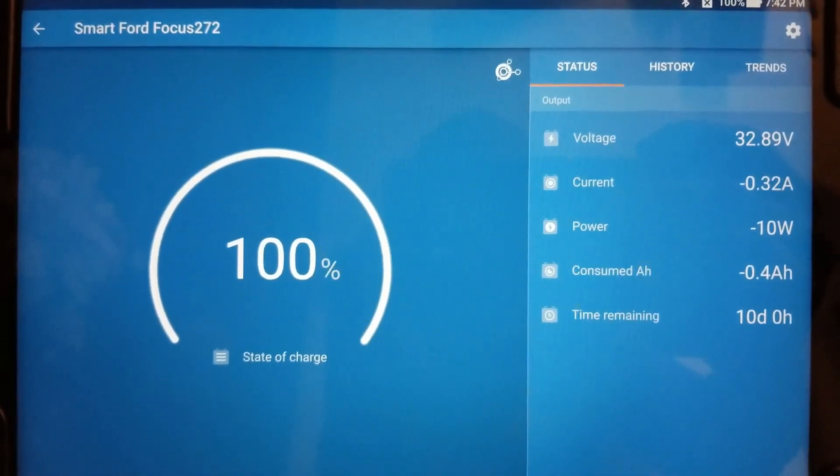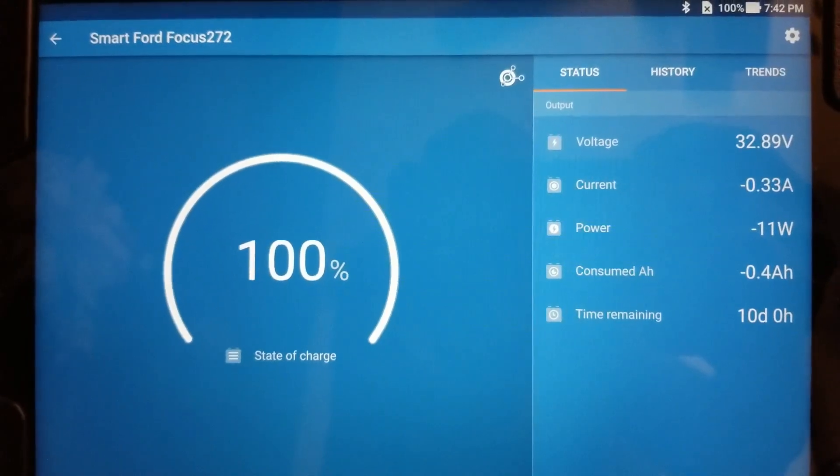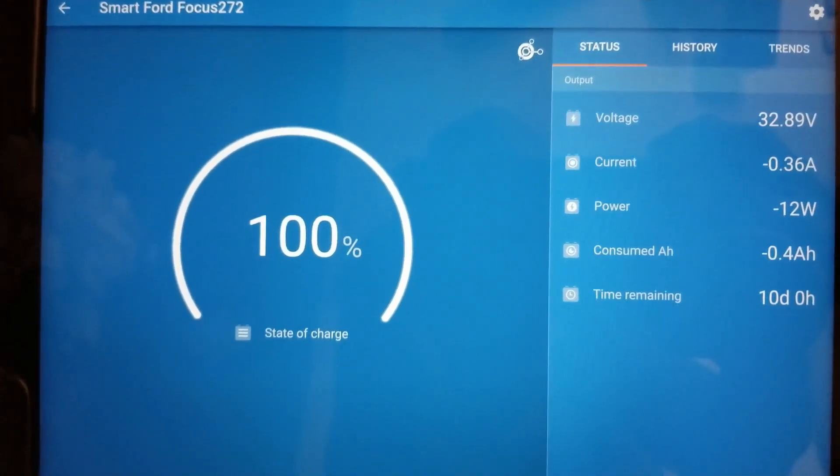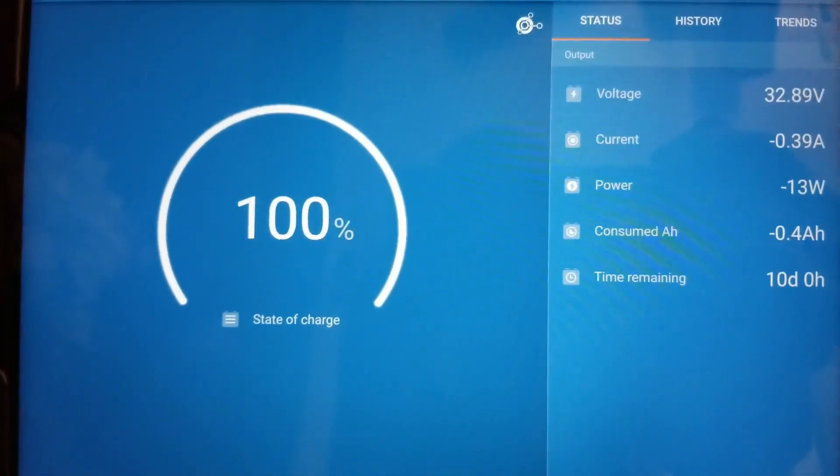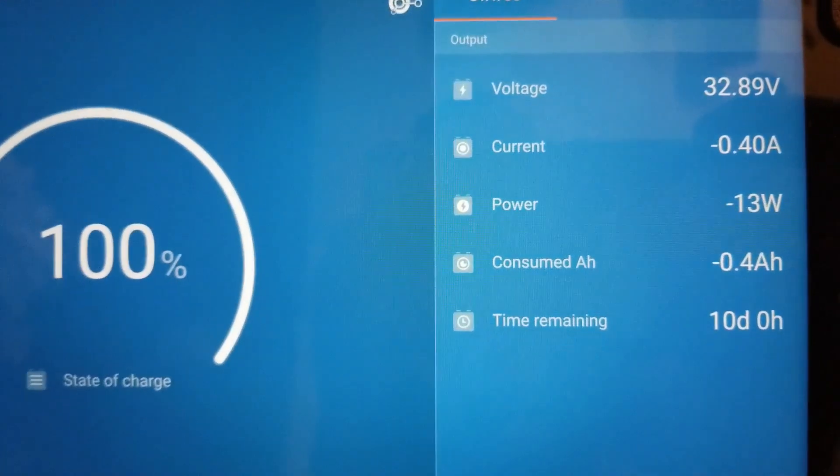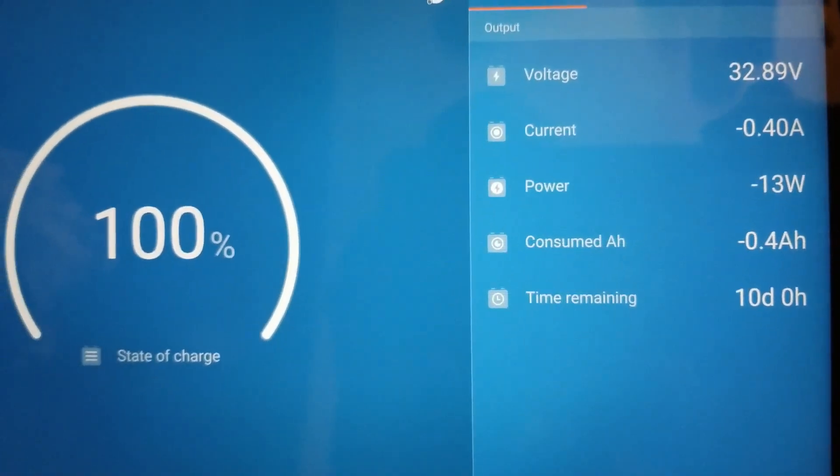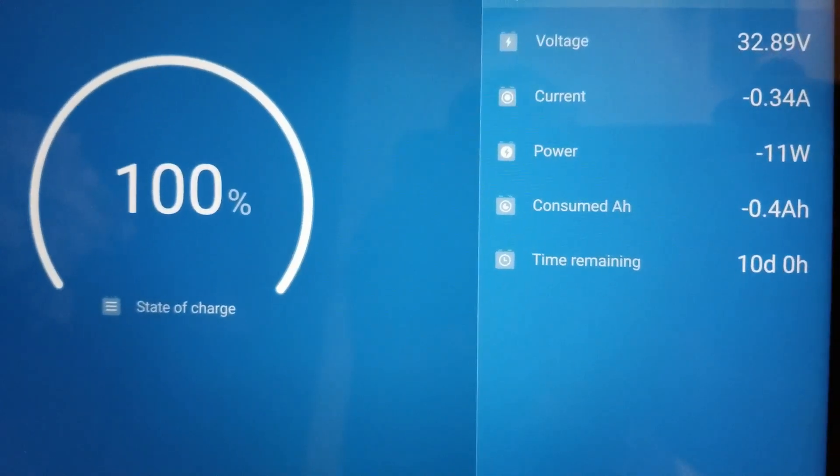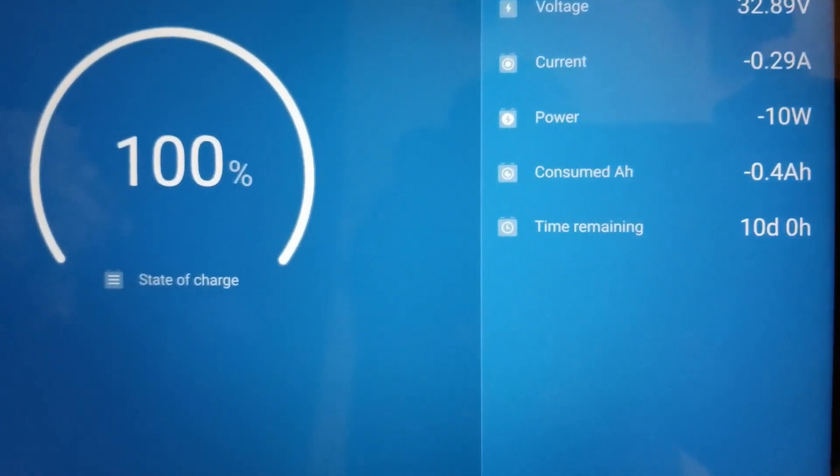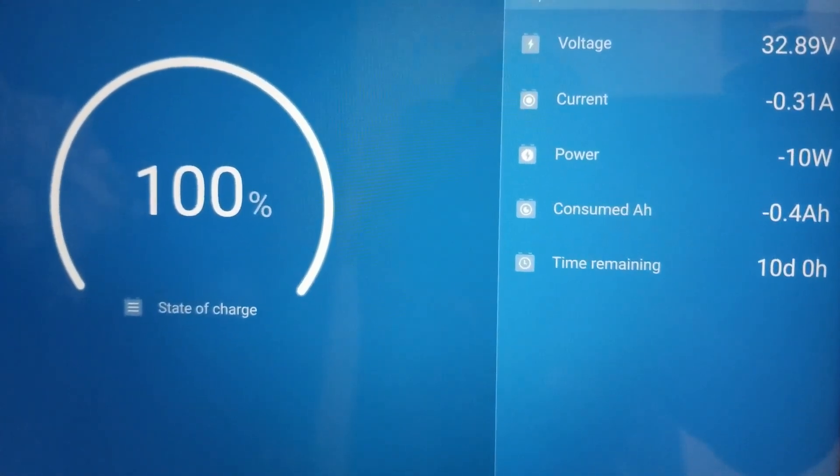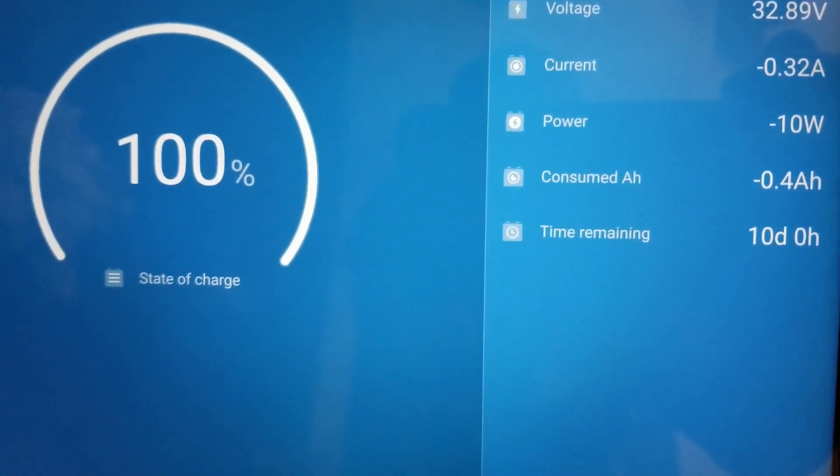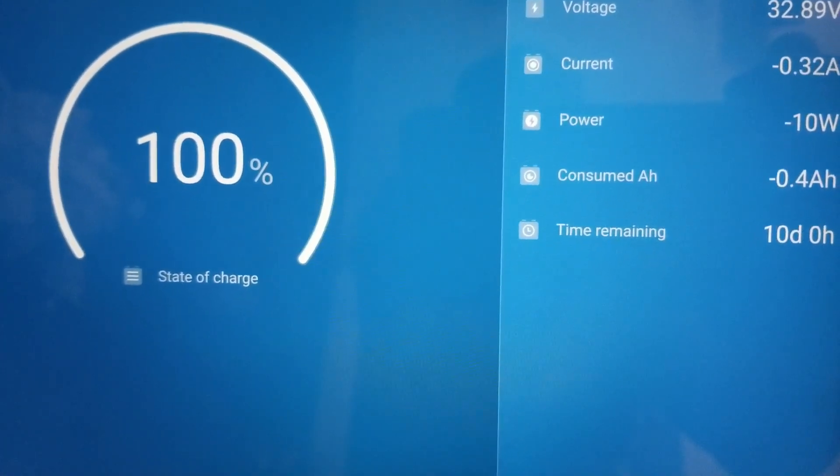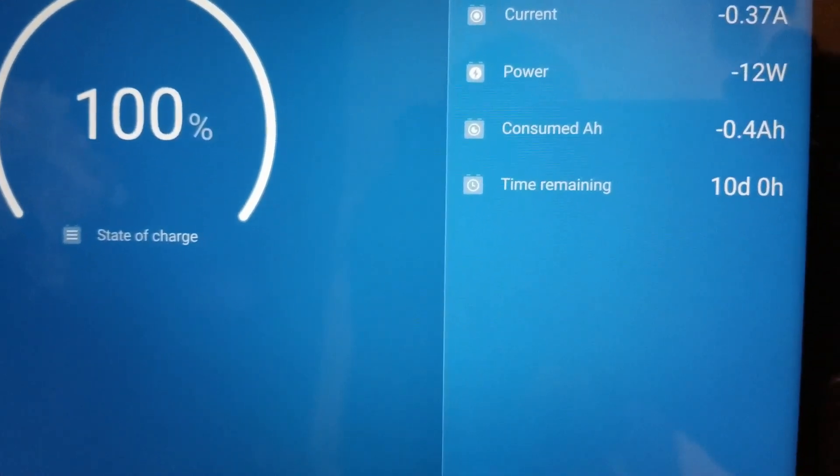I want to share with you guys about efficiency on the Outback Power systems or Outback Power inverters for off-grid. This Outback Power is now at rest in power saving mode. Look at that, it's pulling 9 to 10 watts on standby and 0.32 amps.